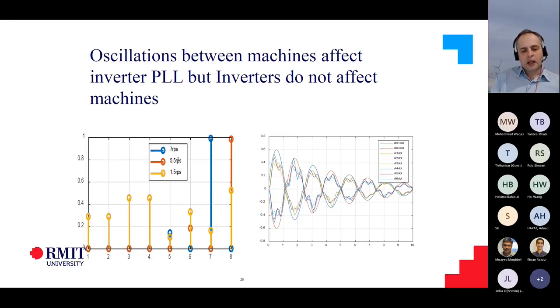Now, this is going to be a problem because many of the controllers in the old power system were designed specifically for specific frequencies. We had some controllers designed for local modes, and some designed for low frequency inter-area modes in the range of 0.5 to 1 hertz. But now, when we are dealing with a system that is dynamically changing, we don't have a constant rotating inertia all the time—the inertia will be different across different points of the system. That means the modes we'll be dealing with in the system are going to change, and we are seeing lots of oscillation modes in the range of 5 to 10 hertz. Because they are changing, it's not easy to design some sort of permanent controller for them, so we will need some adaptive controller to tackle those oscillations in the system, which will also impact the inverters.